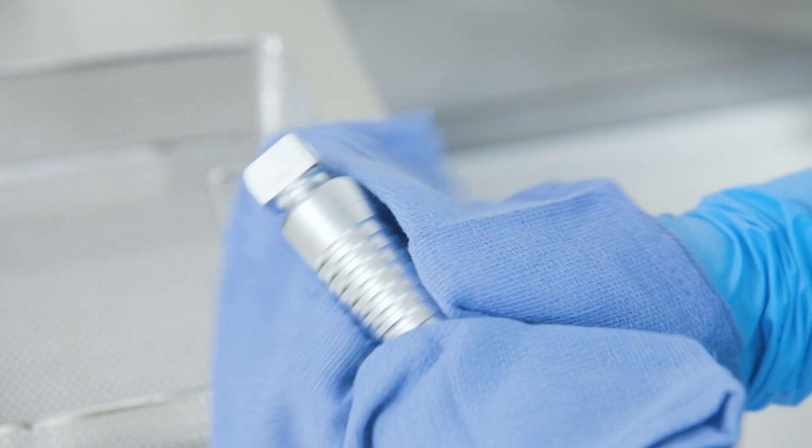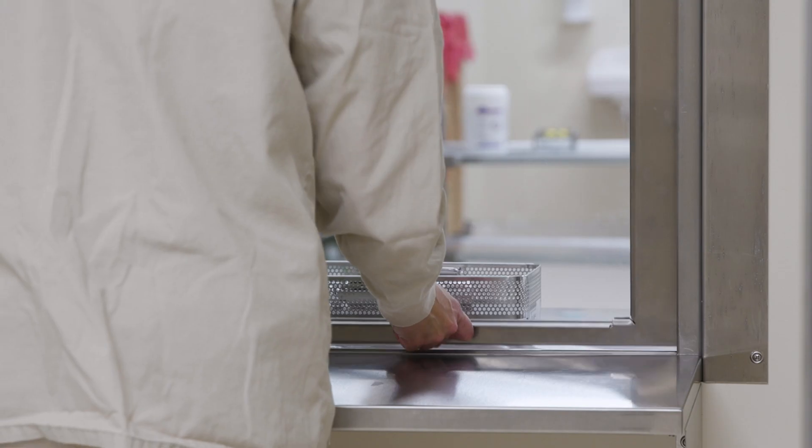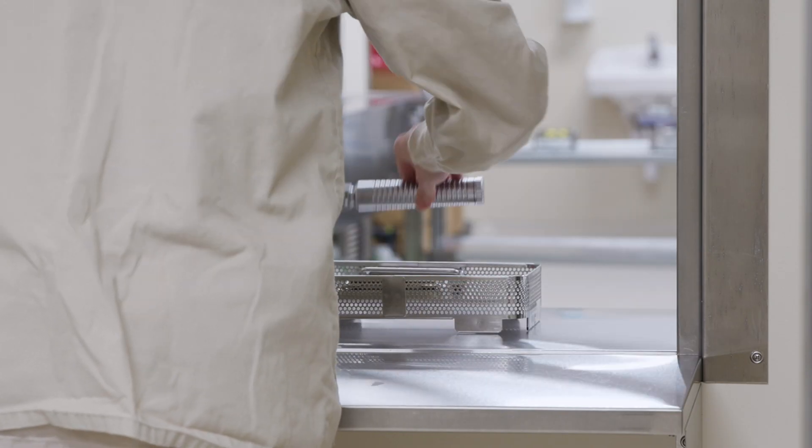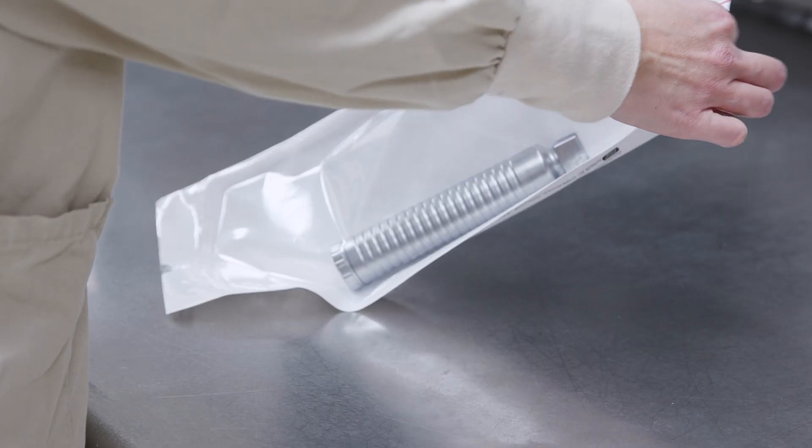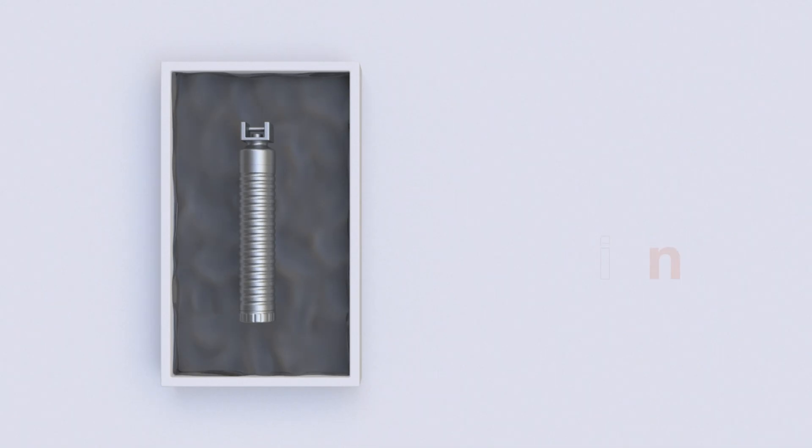The EasyClean handle is also the only laryngoscope handle on the market that can be sterilized completely without disassembly of any kind. This ensures that the handle is simple for sterile processing departments to reprocess. It's also important that the cleaning process for your products can be compliant with all regulatory and auditing agencies.